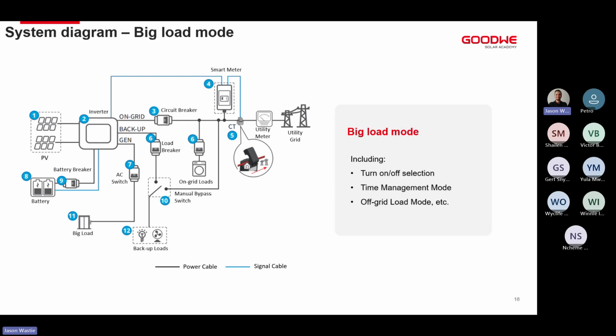Or we can have it based on certain times of the day, run it during whatever times we want it to. Within the time management mode setting, we also have an intelligent setting, which means that when we are running and it's during the day, we've got our batteries running full, there's enough PV to provide to all of our loads, and that port is off. When there is enough power sufficient, it will open that port up and allow those loads to run.